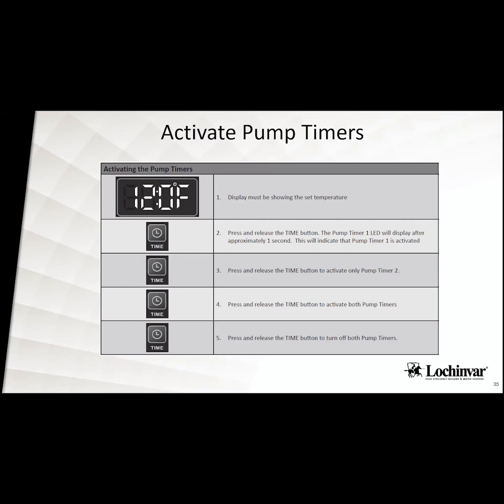So if you've got customers that want to have the pump starting at 5 a.m. to 10 a.m. and then from 4 p.m. to midnight, or you can have both timers set up from 12 a.m. to 12 p.m. and 12 p.m. to 12 a.m. You could have that recirc running 24/7. You can set up those 2 timers however you want them to overlap or not overlap. But it's just a very simple pump timer to make sure that they have hot water during the times that they typically use hot water.